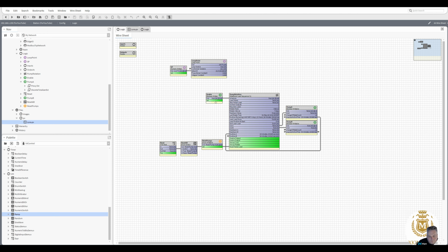So what you could do here is, when we actually ask the schedule to run, let's just put this into fault again, because we're not getting a feedback on here. Feedback, where are we? Feedback here, A and B. But it's going into fault. That's the reason why they're going into fault.